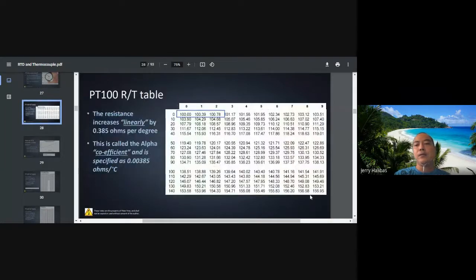Okay? So we go now to the table, no? So this is the table for a PT100. You notice, at 0, the 0 column, the 0 row, it's 100 ohms. When you go to the first column, it means 1 degree centigrade. So 100.39, 2 degrees centigrade, 100.78 ohms, until 9 degrees centigrade, you're expecting 103.51 ohms. At 10, you are at 103.9. At 20, 107.79. At 28, here is 110.9.